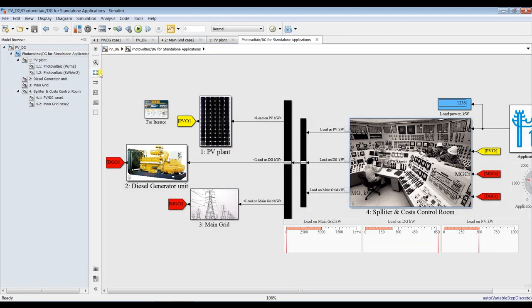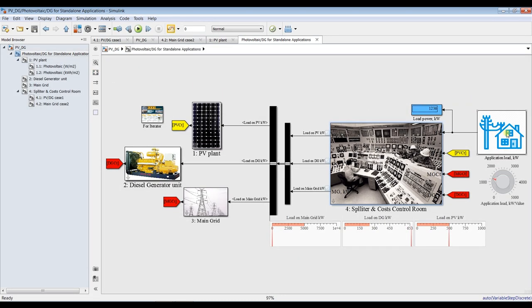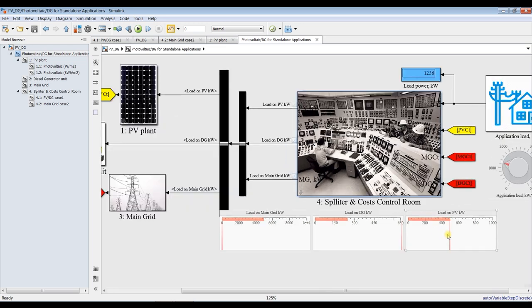For around 1,200 kilowatts of power, there is about 500 kilowatts of load on PV, and there is more load on diesel generator, and there is zero load on main grid power.